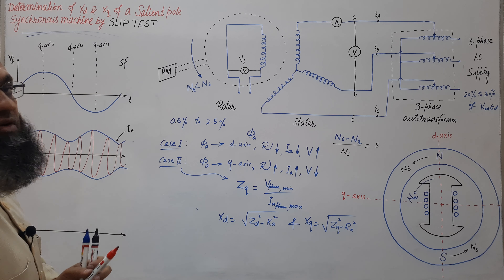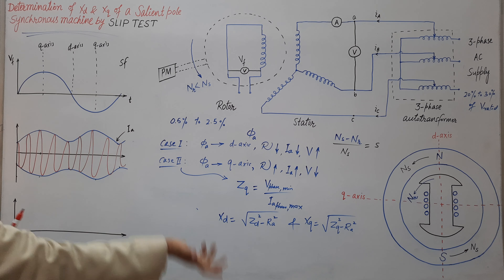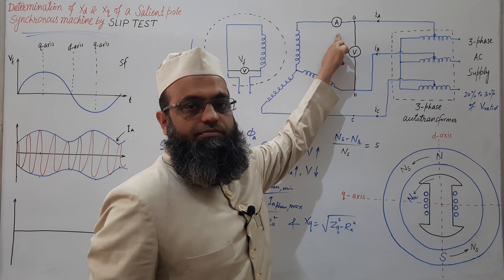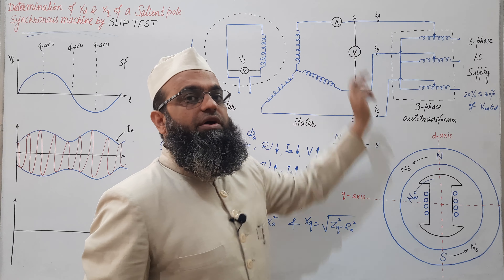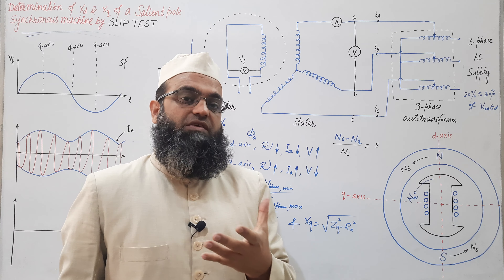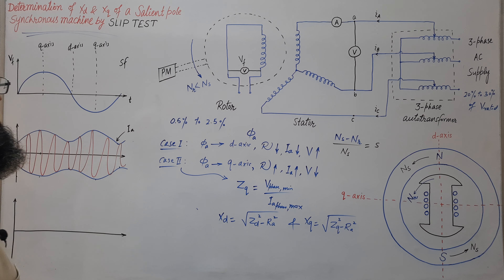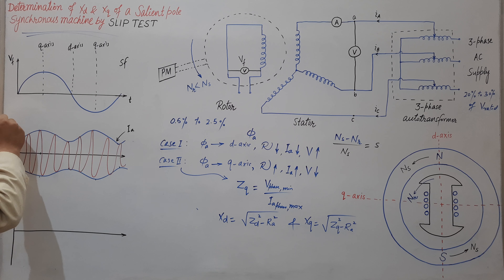So in one second, for 2 percent slip with supply frequency of 50 Hz, we will have two cycles of this variation in Ia observed by this ammeter. That is why it is difficult to observe two such cyclic readings in one second — that is why we need to keep the slip as low as possible. This is the armature current Ia.